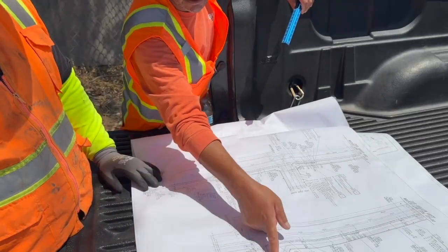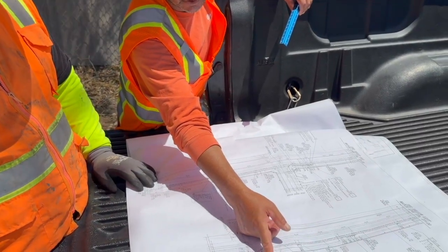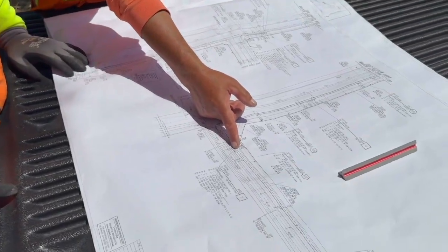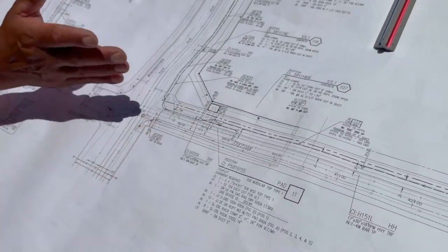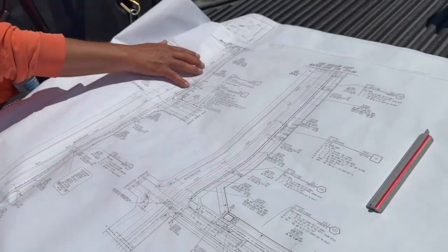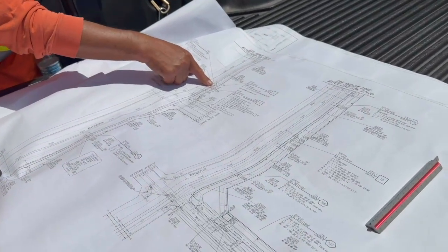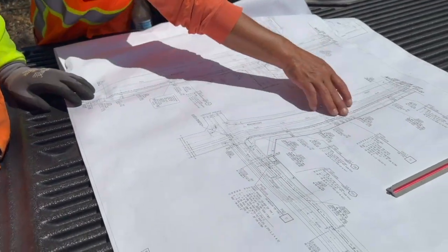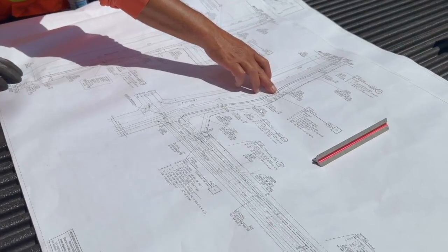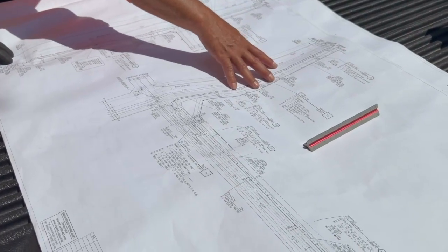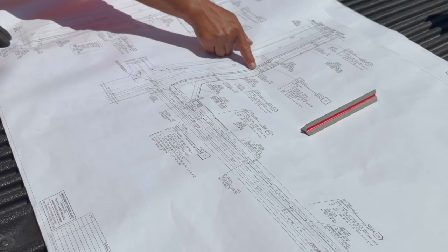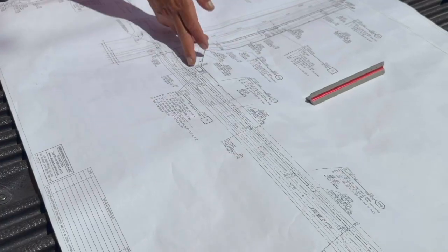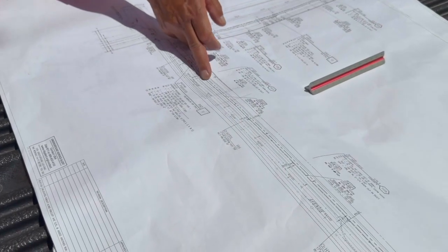to make sure what I see right here, that is trench that is going behind and the trench that is going inside, going through the back. So we need to put attention, because after this point, specifically this point, the 3-inch pipe becomes a secondary system. So it doesn't go through the box. All the secondary system doesn't go through the primary box. So now it's going astray, goes to the handhole, continues in the same package, but as soon as we enter the box, that secondary package is going outside and then going back to the trench.